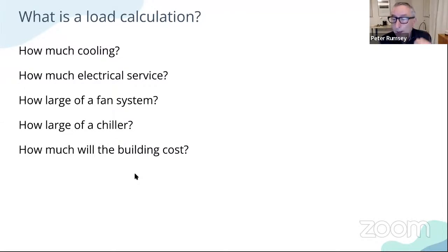So we're going to talk about how we determine these loads, and the idea of right sizing. Right sizing means providing the building with just the right amount of equipment to meet the load. So it's making sure that if I need 1 kilowatt of cooling, or using BTUs, 12,000 BTUs is 1 ton of cooling.